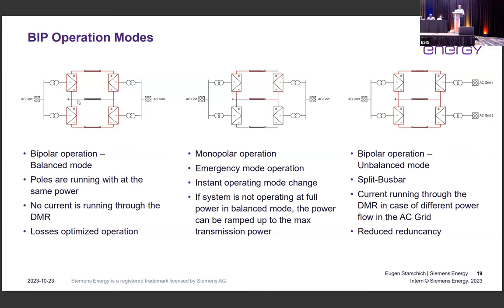In case of a fault, we automatically switch to the monopolar operation. The monopolar operation is that the current is going through the DMR. That means, for example, in case of a fault in this lower pole, you can still operate with the remaining pole. And what is usually done, if you are running in the balance mode with just 50% power transmission capability and you have a fault in the monopolar system, you can ramp up the power in the remaining pole to compensate a loss of pole if possible.